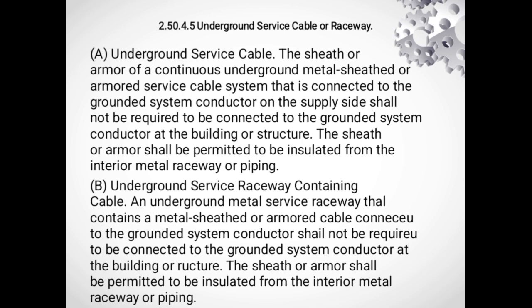Section 2.50.4.5 addresses underground service cables and raceway. Letter A states that the metal sheath of an underground service cable does not need to be connected to the grounding electrode at the building if it's already effectively grounded on the supply side. Letter B extends this to underground service raceway containing metal sheathed cable if the sheath is grounded at the source. A redundant ground at the building is typically unnecessary. This avoids potential circulating currents.